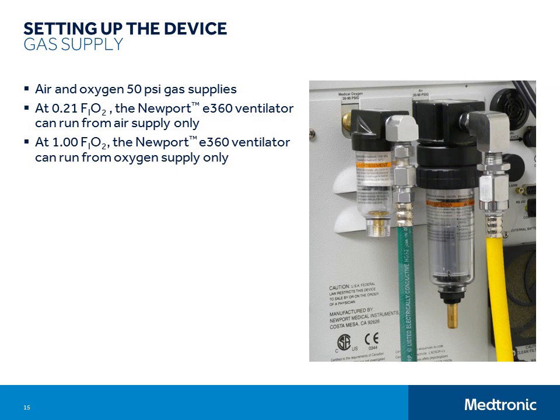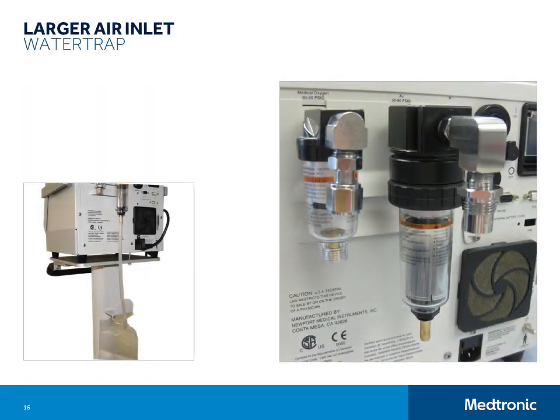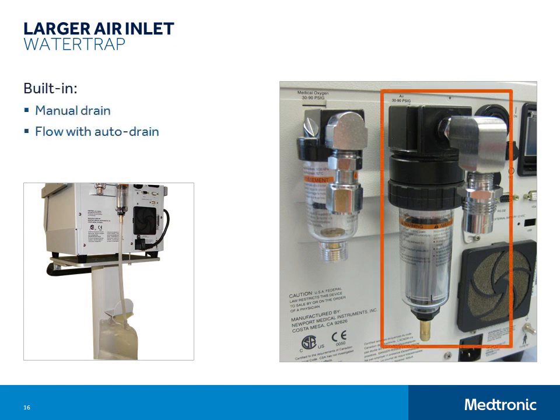We know that some climates make it very difficult to maintain completely dry air supplies, so the E360 is equipped with a larger air inlet water trap to help minimize the chances of water entering the ventilator through the air source gas line. This air inlet water trap comes equipped with manual and auto drain features. You should check the jar regularly and manually drain any accumulated water into an approved receptacle.